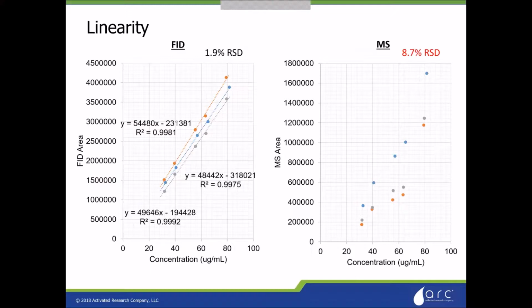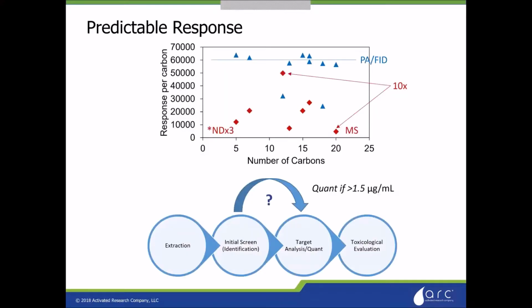And another benefit here is you're getting much higher linearity using an FID rather than a mass spec. The mass spec, because of the way it operates, just can jump around a lot more than an FID, with RSDs a lot higher than what you typically see in an FID. The other benefit here of that pairing and of using a polyarc FID is this predictable response. So if you're looking at E&Ls and you know you only need to target quantify those that are above 1.5 micrograms per milliliter, you would have no idea with a mass spec whether that peak that shows up is 1.5 micrograms per milliliter, because the response can vary tenfold or more. There were actually 3 compounds that weren't detected just because of the ionization cross-section differences of those compounds.